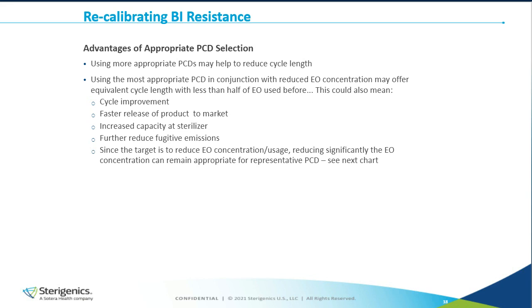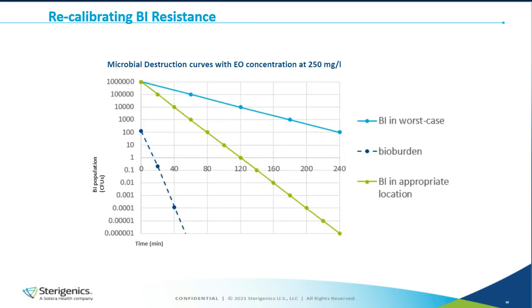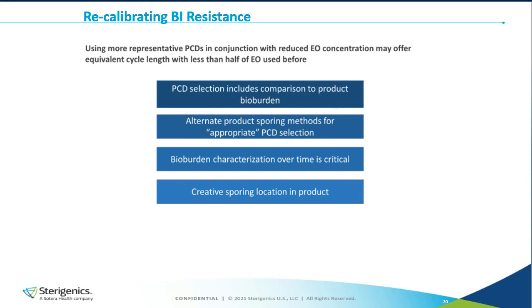But as I said, we are not only targeting to reduce the time. We are focusing on reduction of ethylene oxide concentration. And in the example that I have given here, if we are using the 10 to the 6 BI in the worst case location, now with a concentration at 250 milligram per liter instead of 700, we are not obtaining the kill that we had before. Of course, obviously, with much lower EO concentration, we are not getting the same lethality rate. But we are, with the same exposure time, killing the BI in the new location that is still worst case compared to the bioburden. So it means that there again, we can save time and definitely decrease the EO concentration. So finding the right balance between time, temperature, and concentration is key and essential.